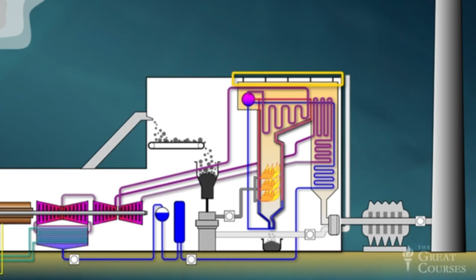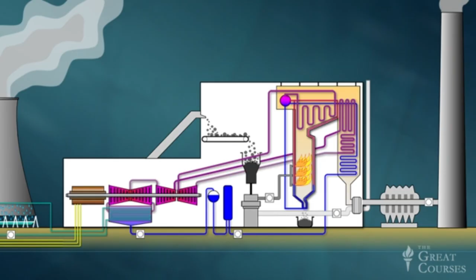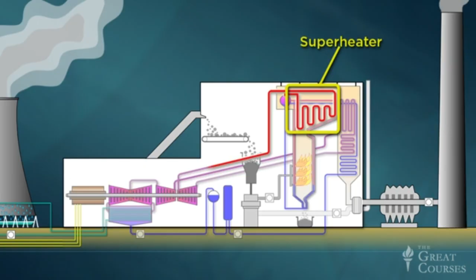Now, according to the laws of thermodynamics, the efficiency of a steam power cycle can be improved by increasing the temperature of the steam that's fed into the turbine. And that's why the high-pressure steam emerging from the steam drum is now routed through this superheater, suspended within the hottest part of the arch-shaped flue. The superheater is really just a heat exchanger. Intensely hot flue gases flow across its coils, raising the temperature of the steam to about 1,000 degrees Fahrenheit, at which point it's ready for the turbine.